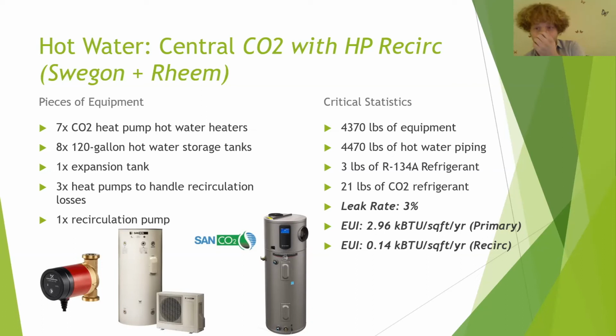So this first system is kind of a hybrid system. You use the Sandens, the CO2 heat pumps, to heat up the bulk of the hot water, because they want to see a really high delta T. What that means is they want to see 45-degree water coming in, and they want to see 140, 160 degree water coming out, which is very unusual for a heat pump, and that's why CO2 is kind of a fun refrigerant. It doesn't work very well for cooling at all, but for heating hot water, it's fantastic.